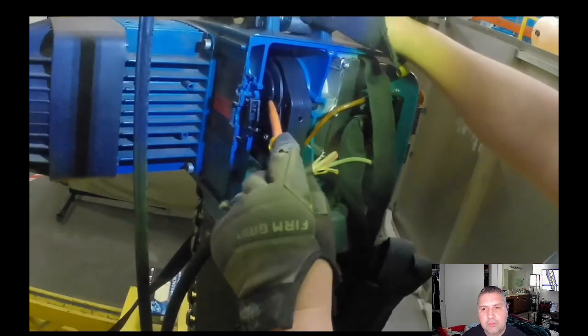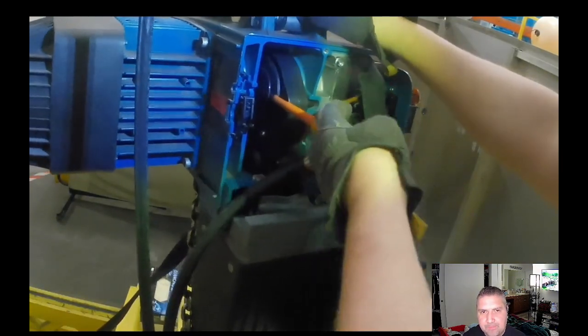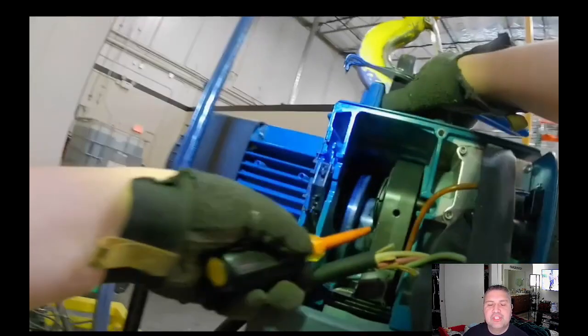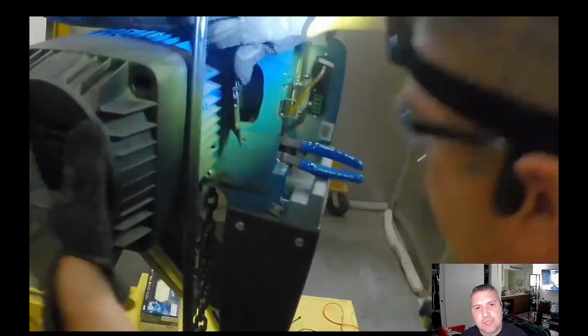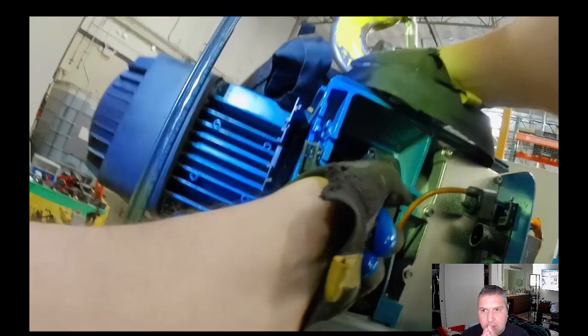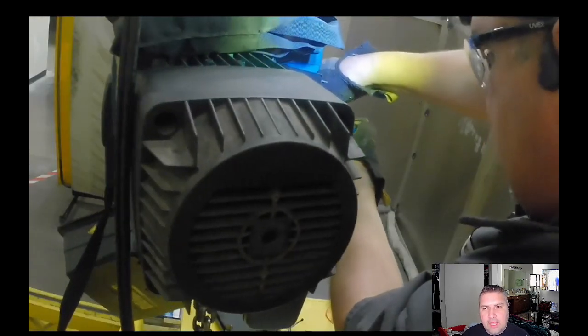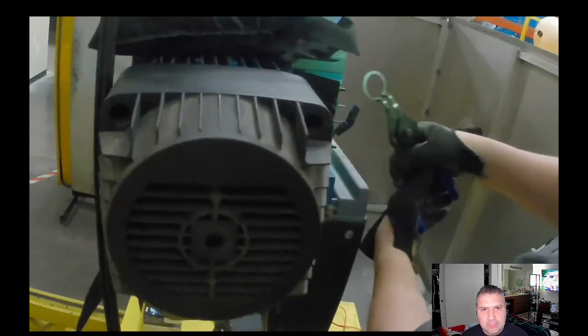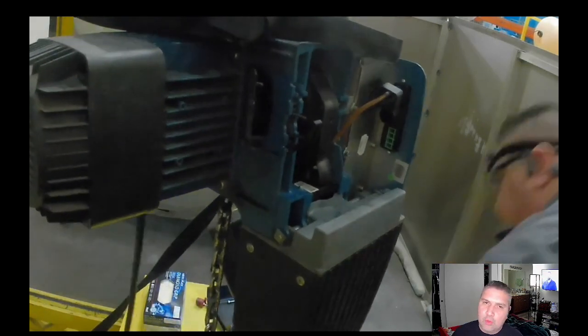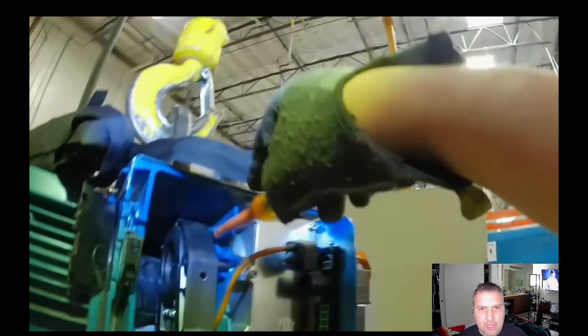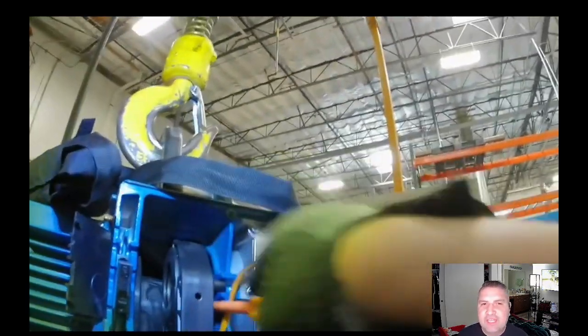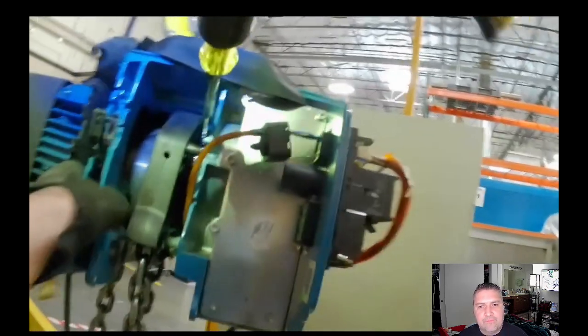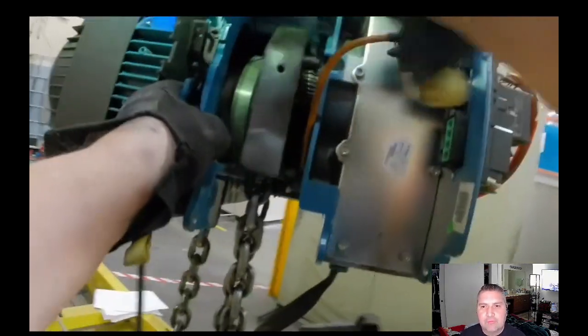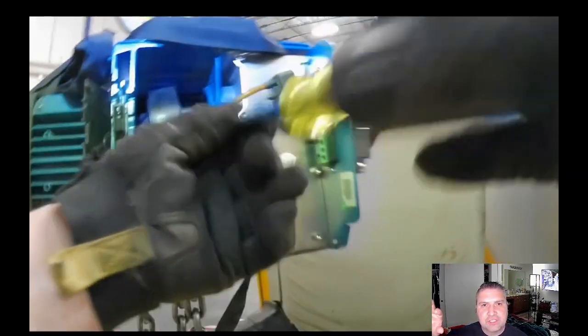It also says to remove the load. So I'm going to remove the chain assembly and have only the motor running, just in case there's binding in the chain assembly. If it's just the motor and the gearbox, that'll give me an idea whether it is in the gearbox or in the motor. But as a troubleshooter, what I can see is that the motor runs in one direction. Usually if a motor's faulted out, it won't run at all, or it'll be shorting, or it'll be blowing fuses. And if a gearbox is faulting out, you'll usually hear a grinding noise or metal to metal. It really makes itself known. All these hoists are essentially a motor into a gearbox with the chain assembly, and that lifts.